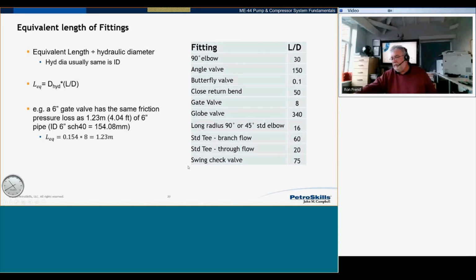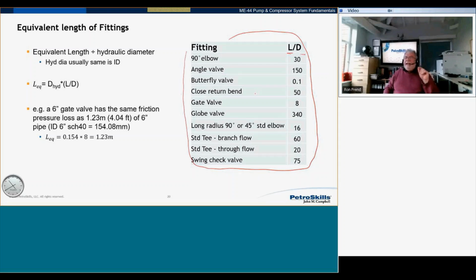Now, there's a quick example here. Let's see if this is working again. Yes, it's working. What we've got is an approximation here of the L over D factor for different fittings. That L represents the equivalent length of straight pipe to give you the same amount of friction loss as this particular fitting. So if you know the internal diameter, the hydraulic diameter, and you know what sort of fitting it is, you can easily calculate the equivalent length.